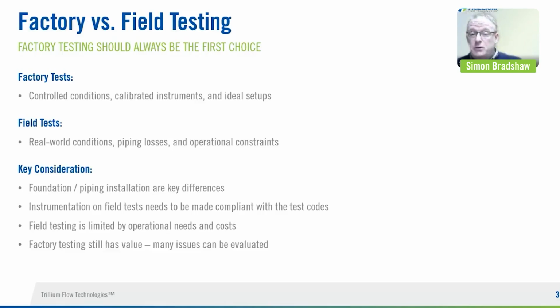In my experience, you have issues around piping, which may not be as good as you would like. You have limits in that they're usually trying to operate the thing at the same time. You may not be able to get to all the flow rates that you're looking for, and the costs are very high because you have to mobilize people to go out there and sit and wait for the right conditions to occur to measure the pump. It can be done. It needs to be very carefully discussed, and it is not cheap. It's not cheap, and it's not easy to do. That's the experience I've had in the times that we've had to do it.